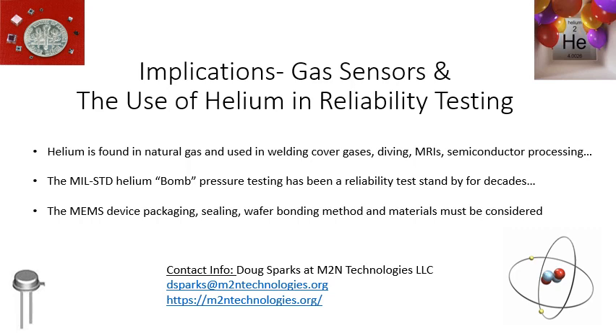So you've got to think, what's the application, what's the device, what are the materials being used, are they resistant to helium diffusion, is the sealing method hermetic, truly hermetic in high pressure helium, maybe it's not. And then again, rethink your reliability testing. You may want to move away from a helium pressure test and do something like krypton or neon, for example, as your pressure gas to look for leakage paths.